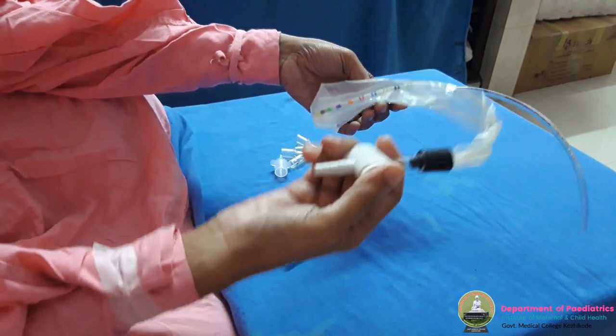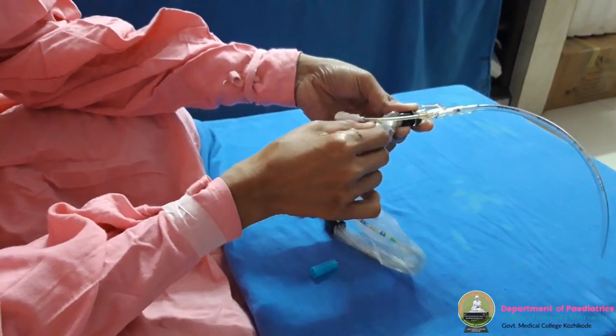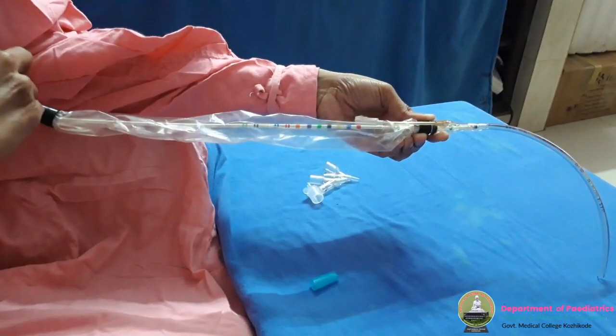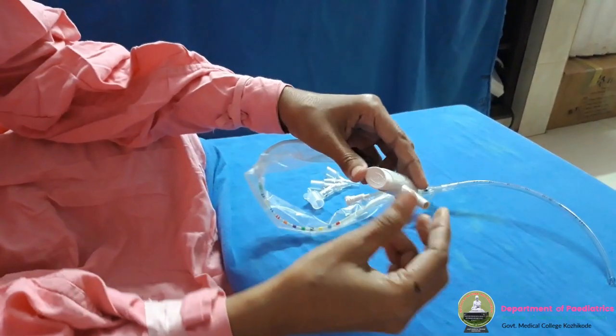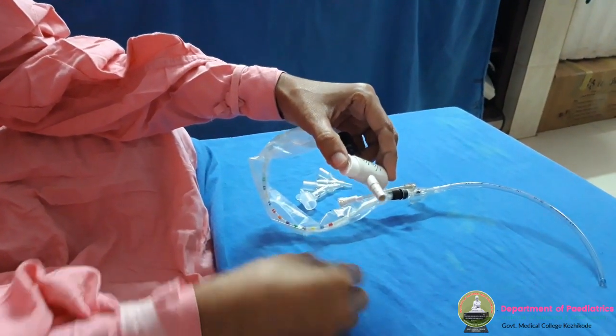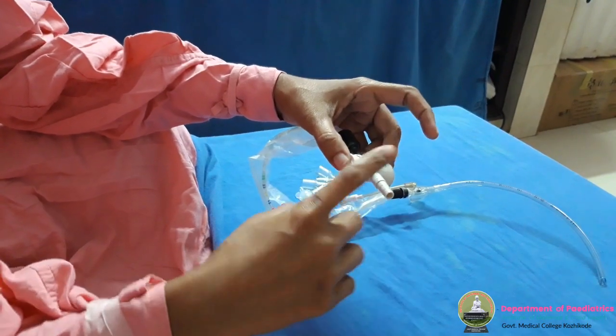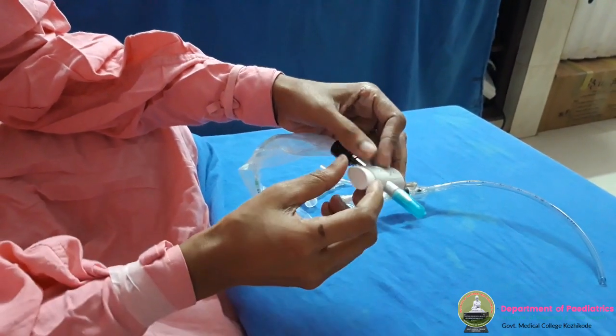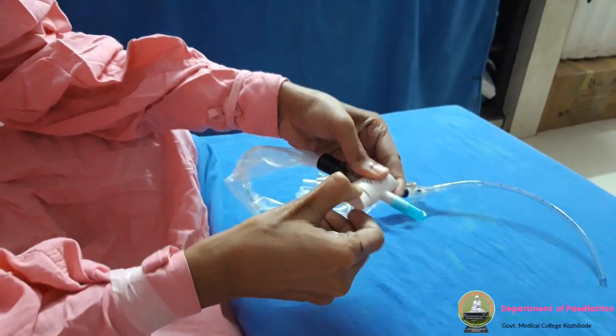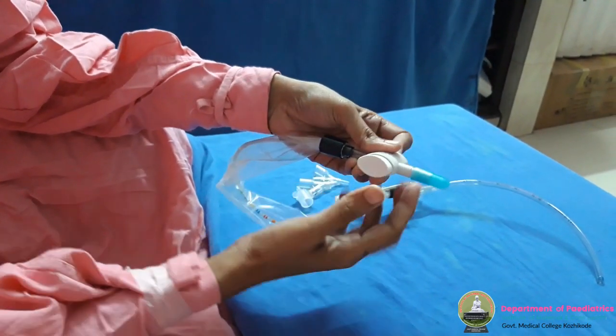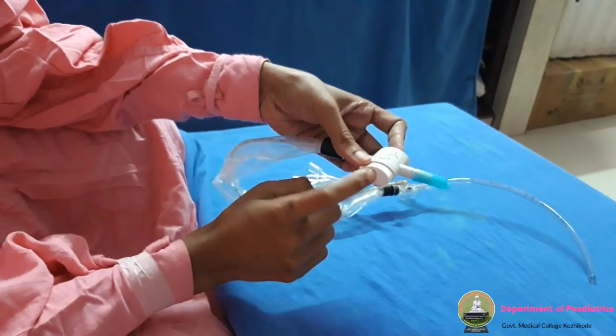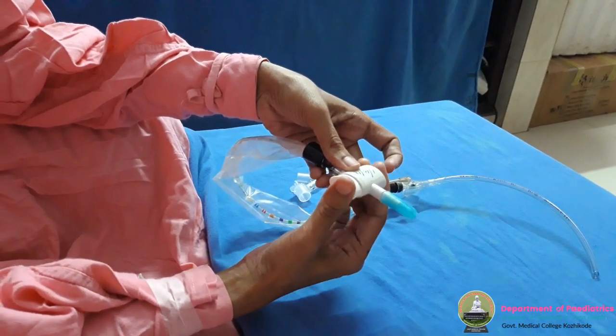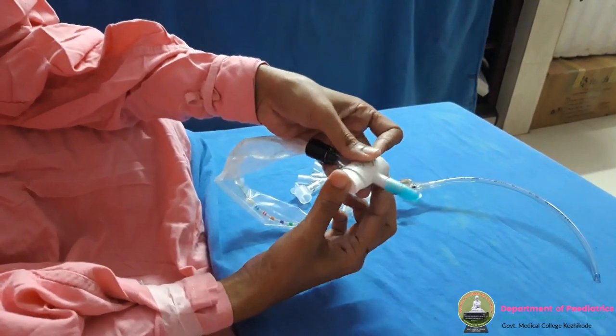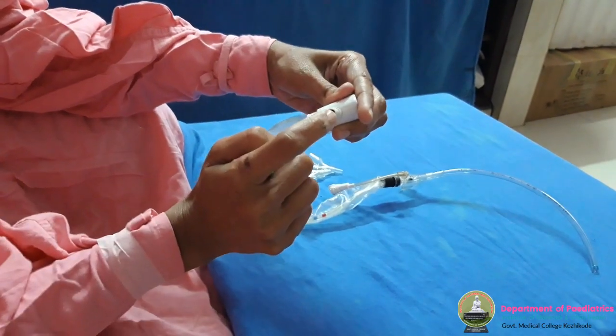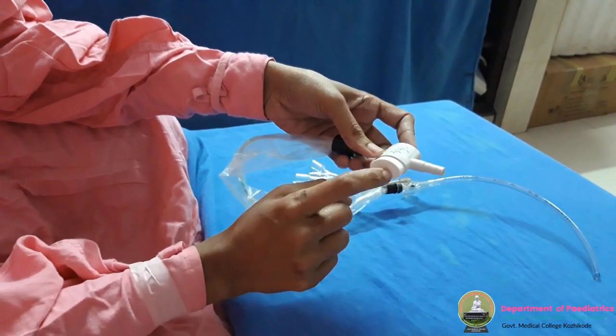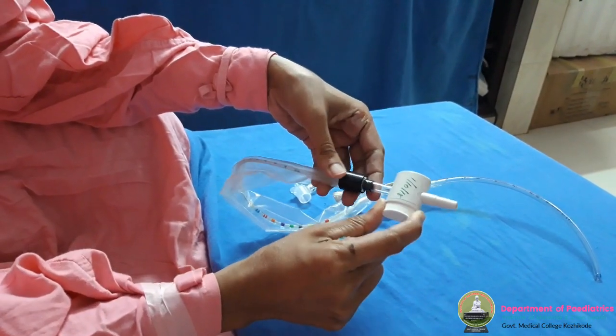That is the way. And after completing, if you want suctioning once again, you can do it once again and the same is to be repeated. After that, you should disconnect the wall suction tube from the end and keep a cap. This cap is with the catheter itself. You can keep it closed and you can lift this part and rotate. Then you cannot press it again. So this is a lock also, to prevent accidentally compressing this area and causing suction. Even if the cap is not there, there is no connection and it is more safe. So this is the method of keeping it when it is not in use.